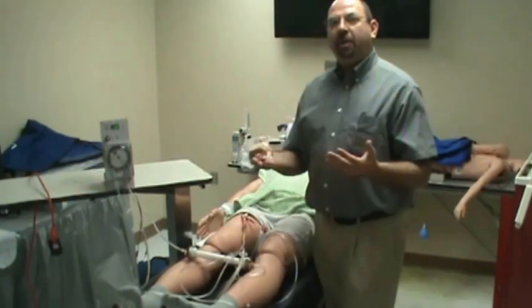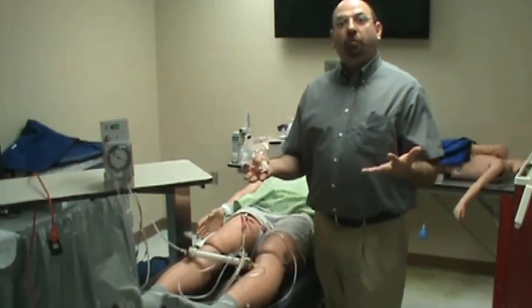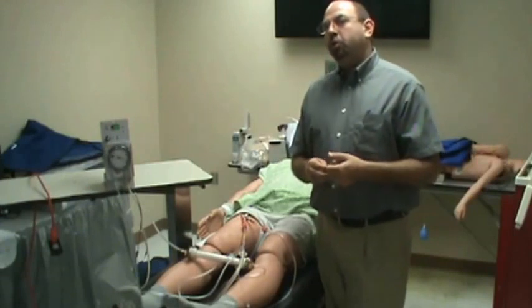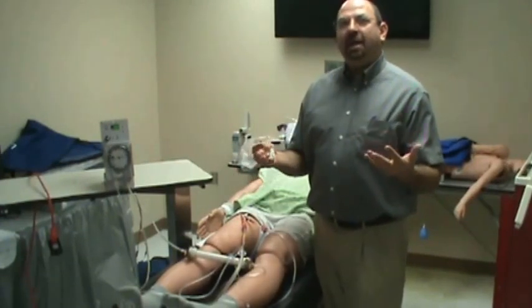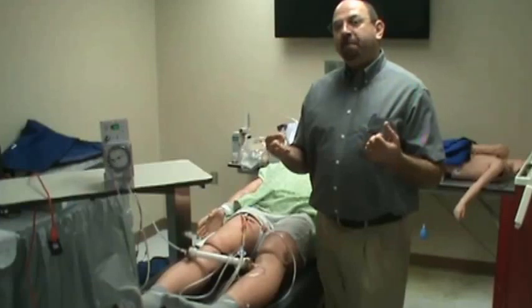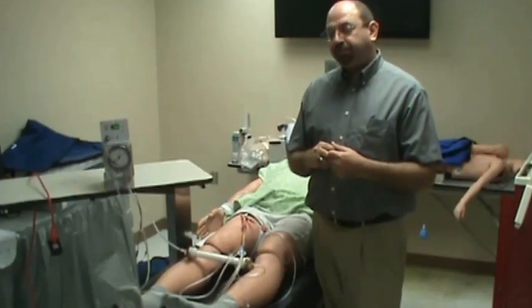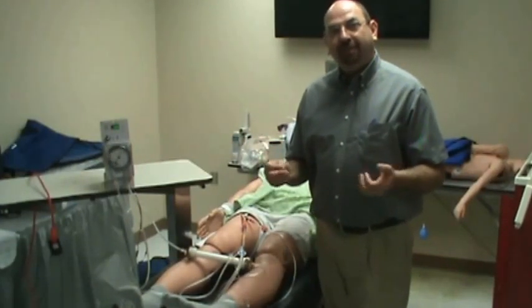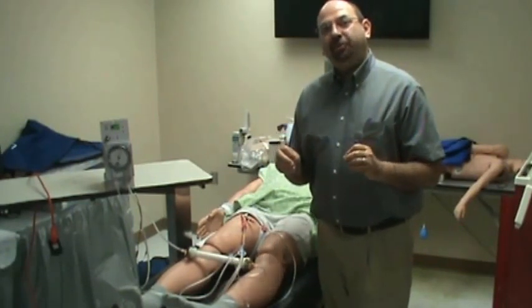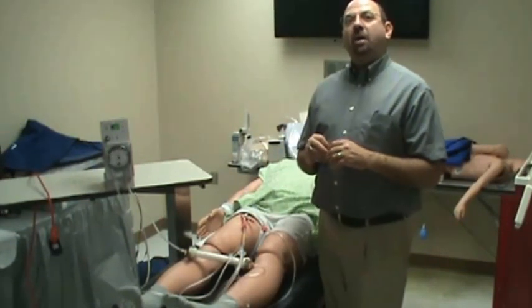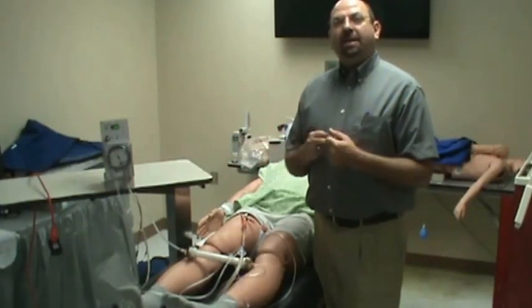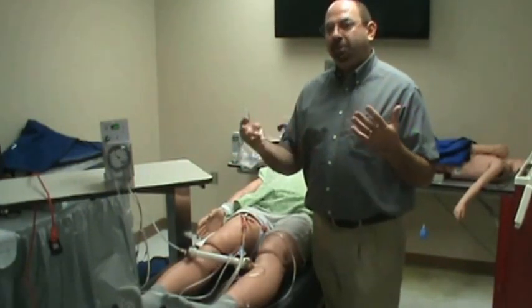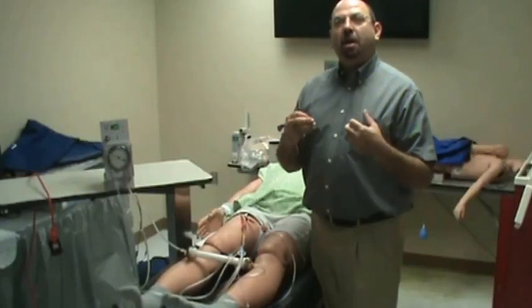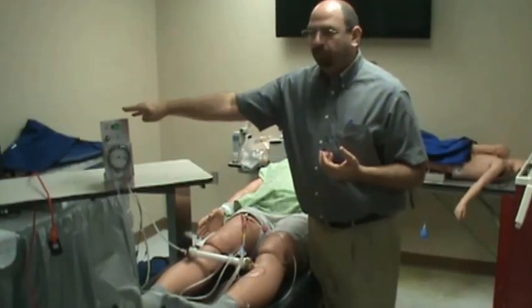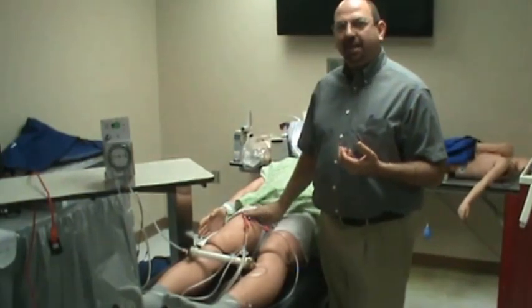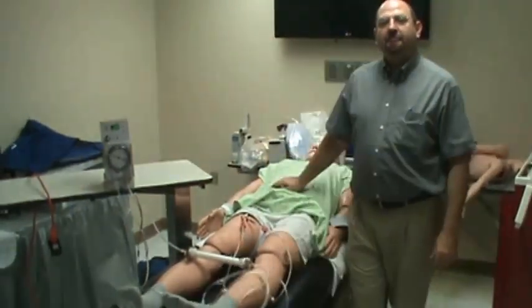You do not have to have the infrastructure related to reverse osmosis water treatment. You don't have to have dialysate jugs and bags, and you don't have to mix powder with water. You don't actually have to have a dialysis machine. You do not have to have technicians who know how to run a dialysis machine and troubleshoot when the machine is not working well or is alarming. All you have to do is have a blood pump, venous access, and the proper tubing.